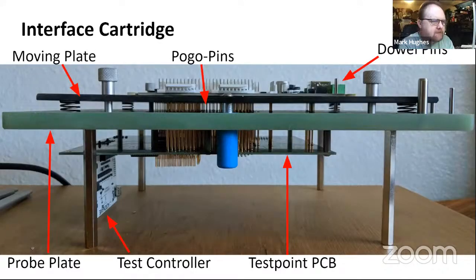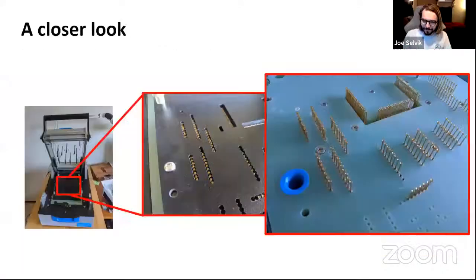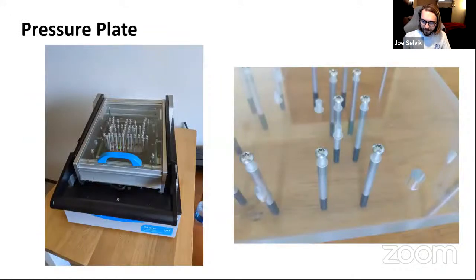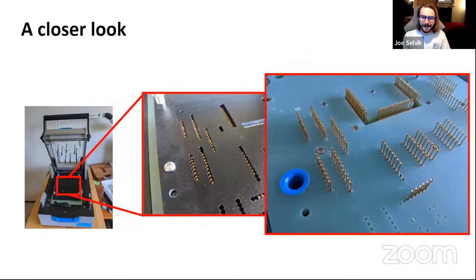Here's a live example where we have each layer inside that cartridge. On the right is the probe plate with all the spring-loaded pins mounted securely into it, and on top of each of those we have cutouts in the moving plate. In that middle image you can see the tips of each probe lined up, providing a flat area for the device under test to be pushed down upon, with each probe lined up to contact the test points underneath.